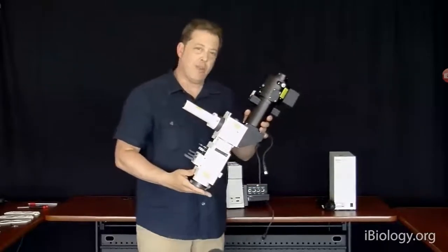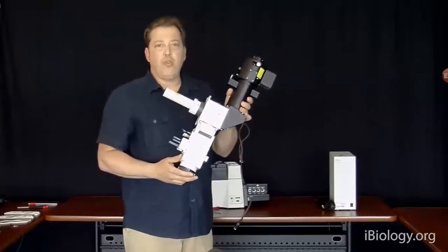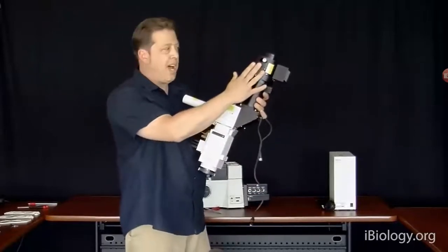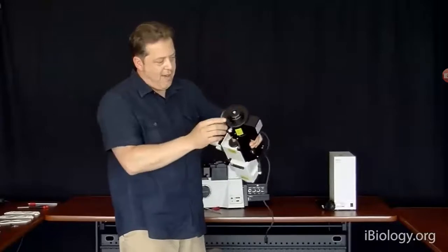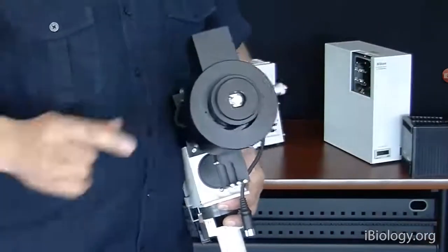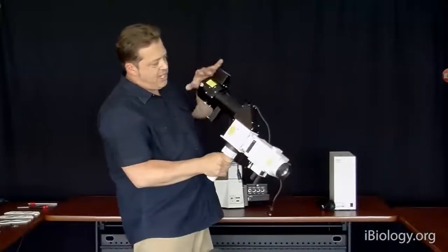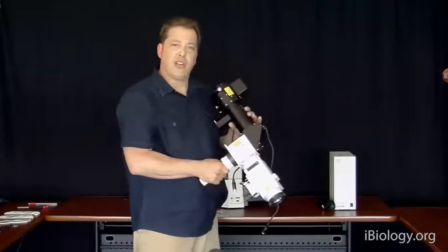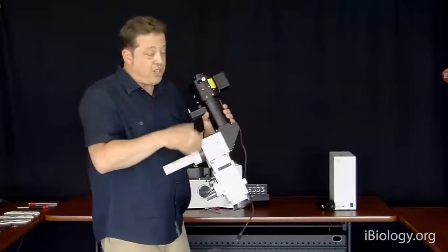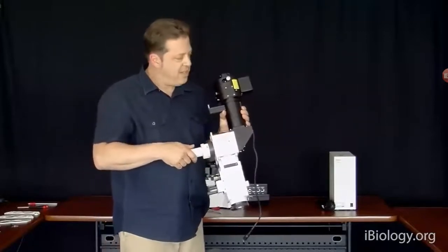Okay, so this is our epi illuminator on the microscope. And this illuminator is actually a sort of dual purpose epi illuminator. It's got laser illumination on one side. And it would have a laser fiber, an optical fiber that can connect to this FC coupler. And what that does is techniques like total internal reflection fluorescence or oblique laser illumination. We also utilize this for our localization super resolution STORM technique.